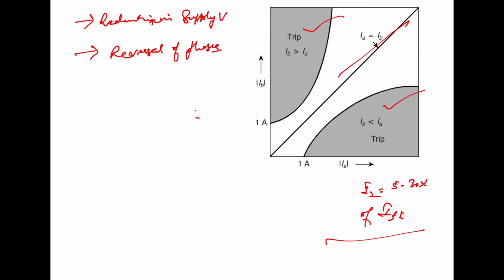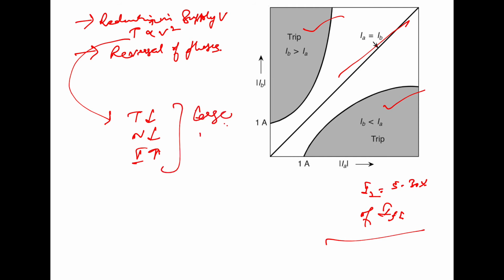Now the other problem is the reduction in the supply voltage. As you know, the torque developed by an induction motor is proportional to the square of the applied voltage. So any small reduction in the voltage has a marked effect on the developed torque. Reduced torque may cause the motor to lose speed, and then the speed would be reduced and the current would be increased. So a large motor should be disconnected when a severe low voltage condition persists for more than a few seconds. Undervoltage relays may be used for protection against the reduced supply voltage.